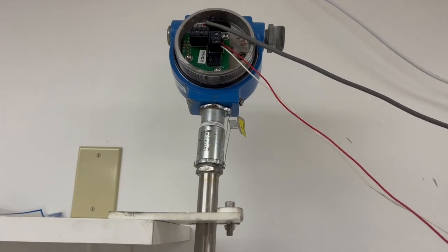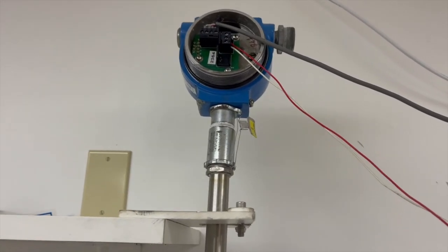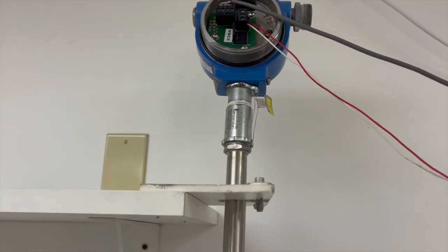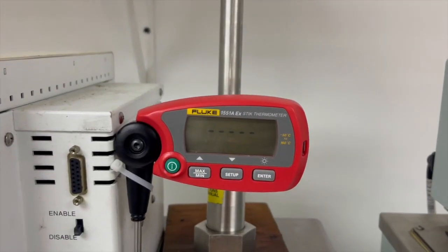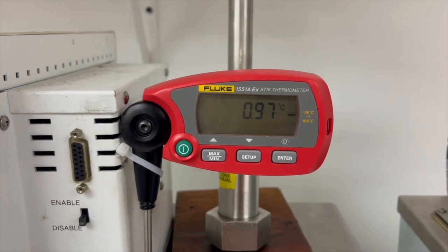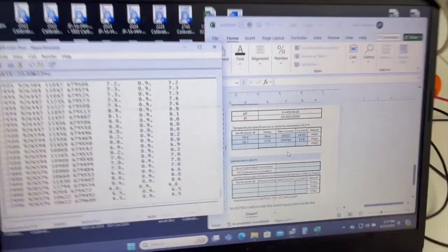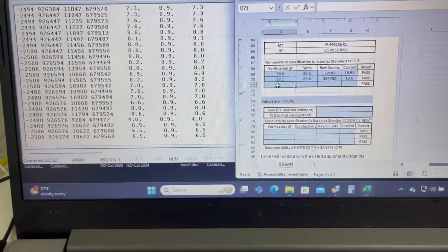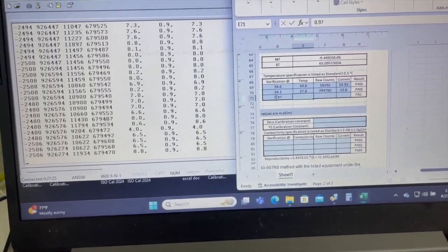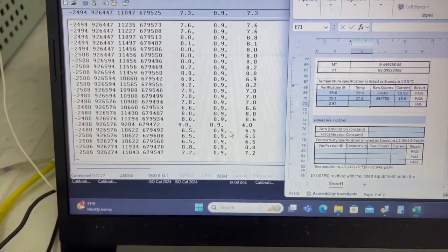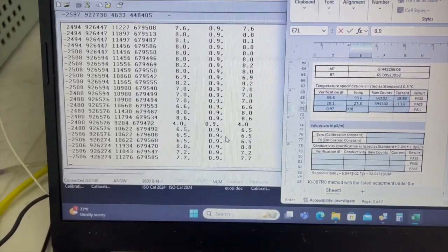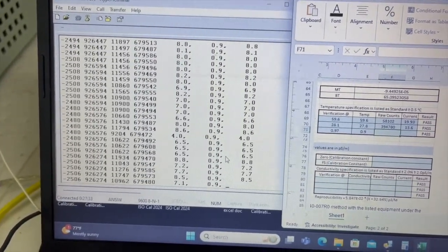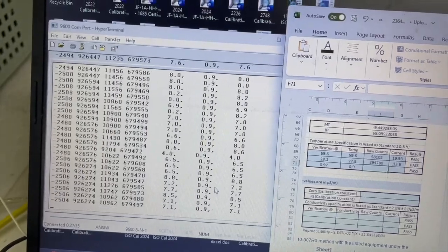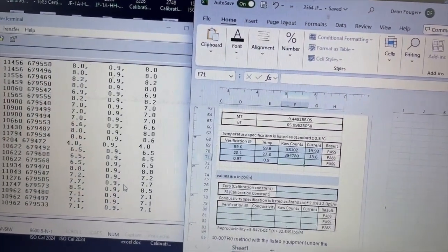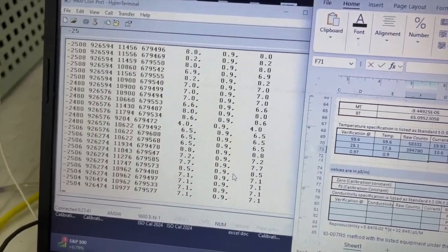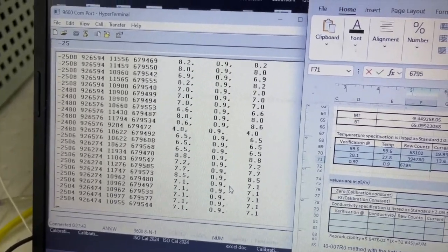Okay, so now that the sensor is soaked at 1 degree, we can verify the 1 degree operation of the unit. So to do that, we're going to turn on our temperature gauge and check, which is 0.97. So we're going to go over here and on our sheet, we're going to type in 0.97. And our sensor's reading 0.9, which is well within the 0.5 variance allowance.